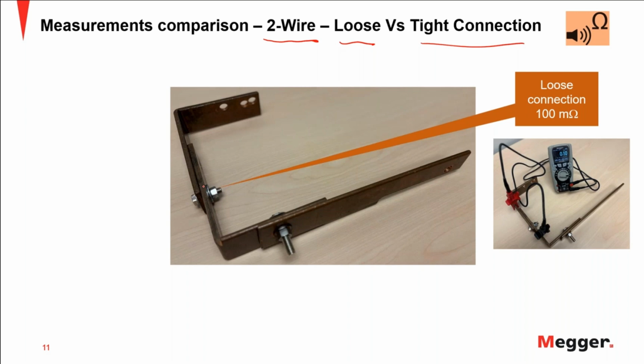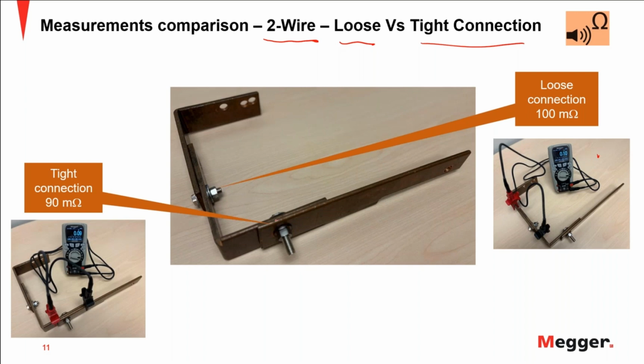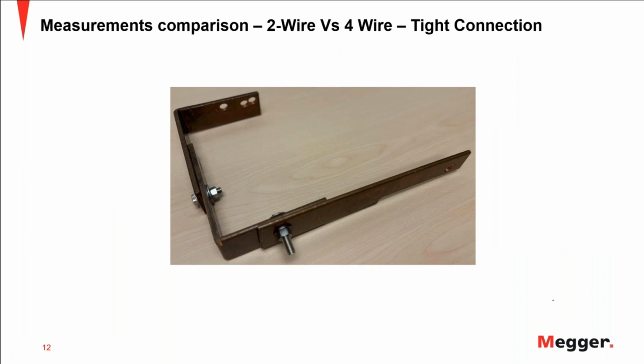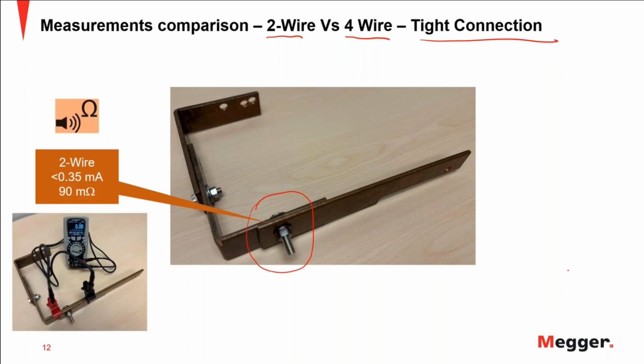And running the test, you can see here I'm running that measurement, and it's giving me a result of 100 milliohms. And then this is a connection that I did use tools to tighten, and it is giving me a measurement of 90 milliohms. So just a difference of 10 milliohms. Now let's use the two-wire method versus the four-wire method on the tight connection. So we're going to focus on this connection here. We already know that with the continuity test, we got the 90 milliohms.